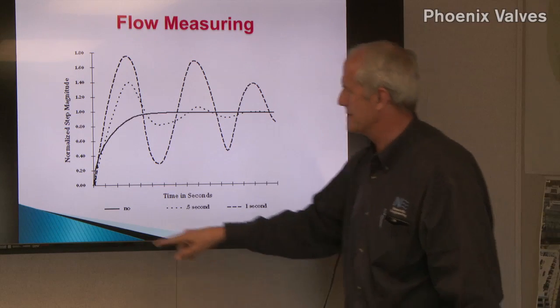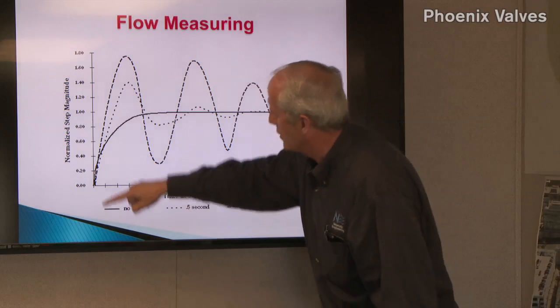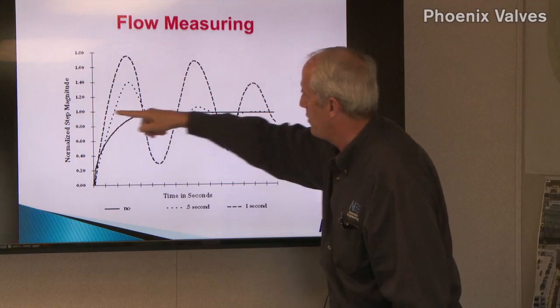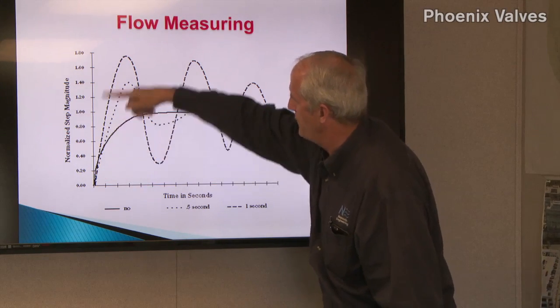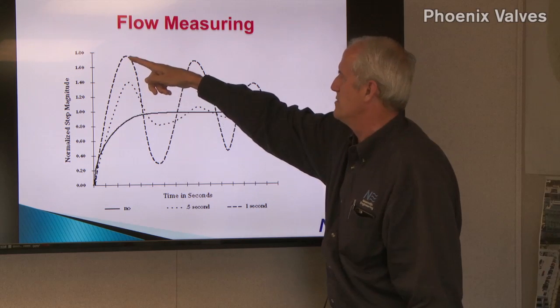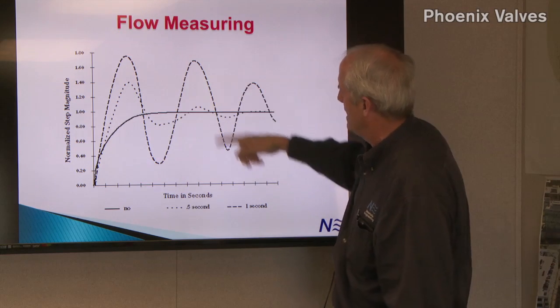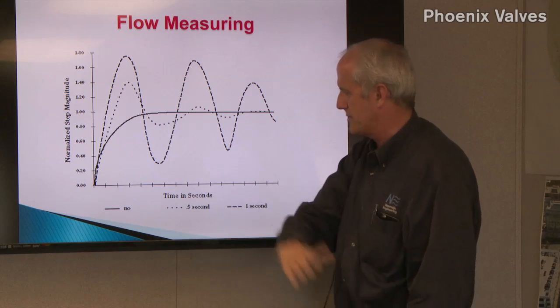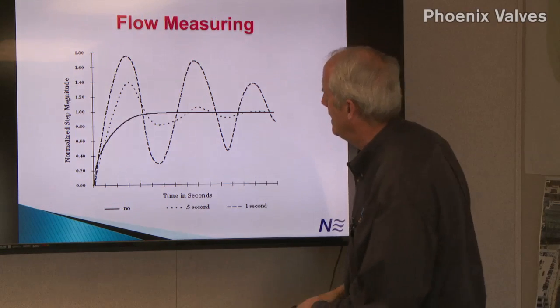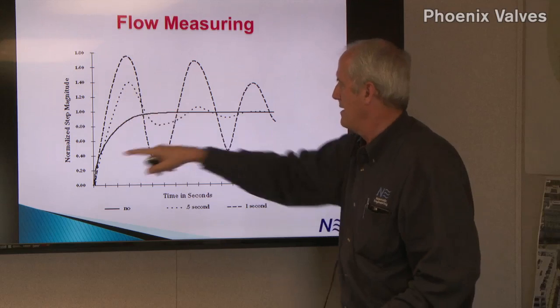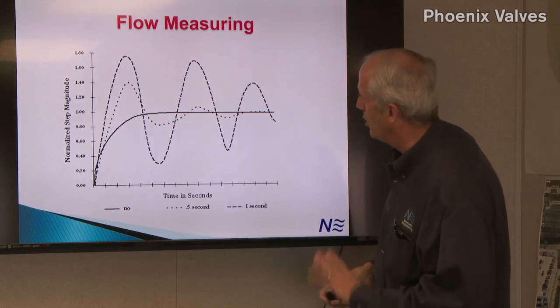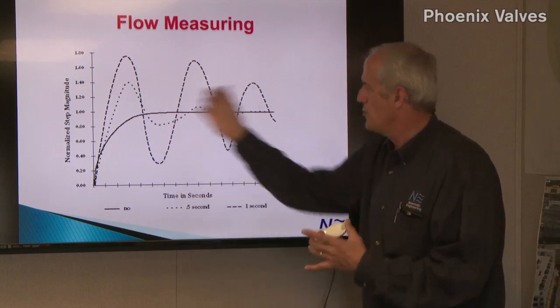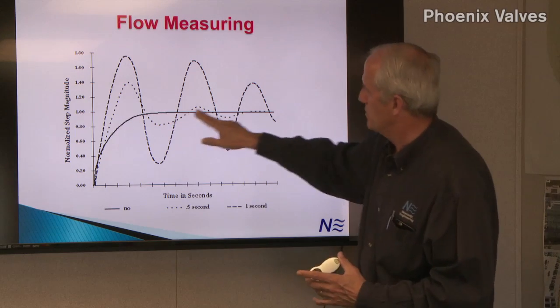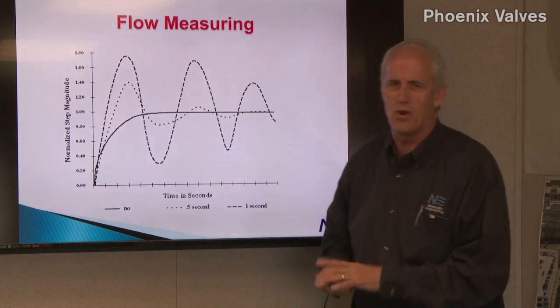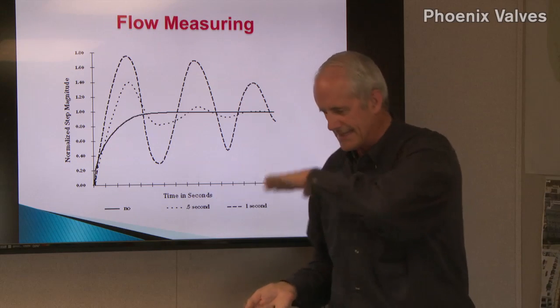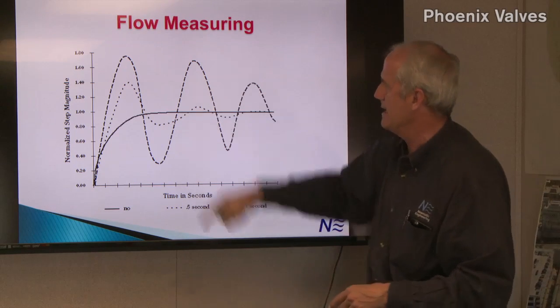In a normal control system, when you're trying to achieve a set point, if you go too fast, you might overshoot, and then you go, oh shoot, we're too strong, we're not strong enough, and you can set up some oscillations. Sometimes you'll see boxes oscillating around. You slow it down, and then when you get to the right speed, you can be stable. So you shoot for stability. The Phoenix valve gives you what's called critically damped control. It responds quickly and stably to where you need to be, and you're not going to get any hunting around.